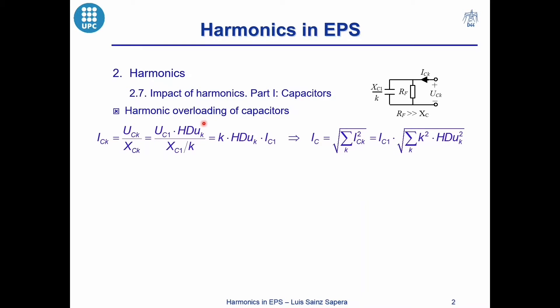Harmonics may produce an overloading of capacitors because the harmonic currents going through these capacitors depend on the harmonic voltages and the harmonic reactance of the capacitor, which decreases with the harmonic order of the voltages. So these harmonic currents flowing through the capacitor bank directly depend on the harmonic voltage distortion and the harmonic order.